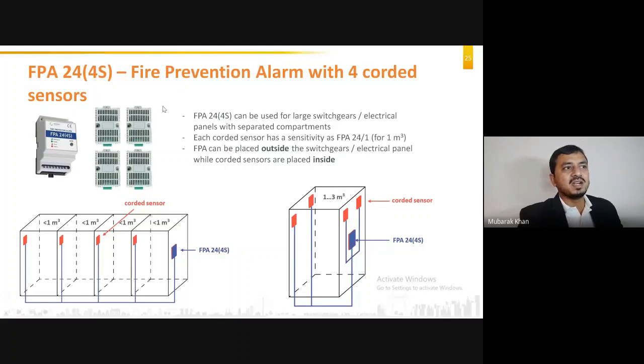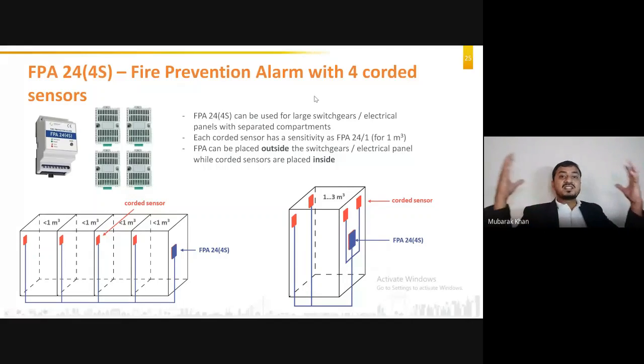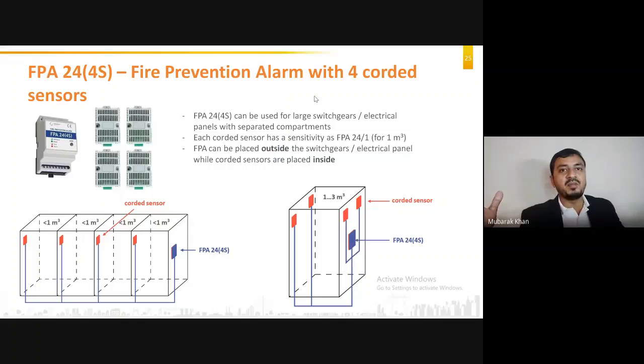This is an FPA with 4 corded sensors. For very large compartments, more than up to 3 meter cube, we can use a multi-channel FPA where sensors are placed at different locations and connected to the FPA, or across multiple cabinets we will have one FPA with multiple sensors in each cabinet. It can be used in both ways.